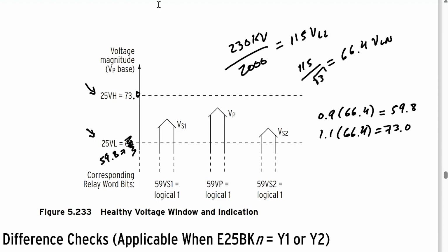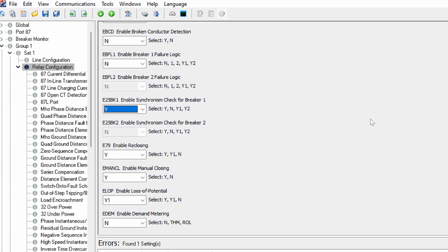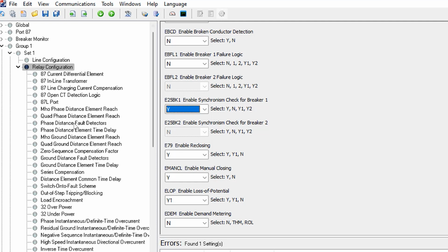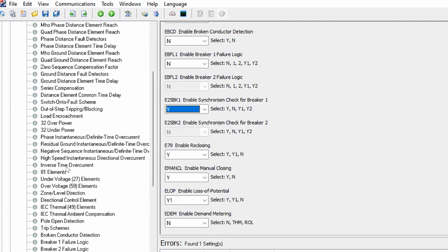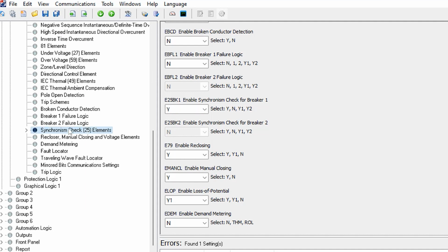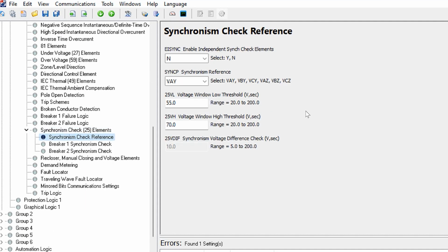All right, so let's go back to the settings file. And in here, we can go to the sync check function to set those bands. So we can go over here. Let me just expand this. We're going to go over here to Synchronism Check elements. Let me expand that. And we first have to define the reference. This is going to be what we're going to compare our bus side voltages to. In our case, it's the line side A phase voltage, which, as I mentioned, is wired to the VAY input of the relay. So the default setting is just fine. In this case, VAY. But again, if you're using another reference, you will need to make sure that this setting is set properly.